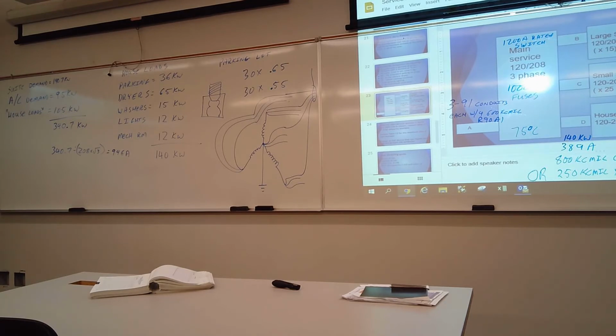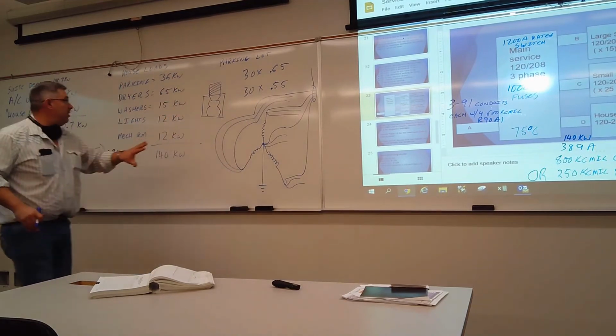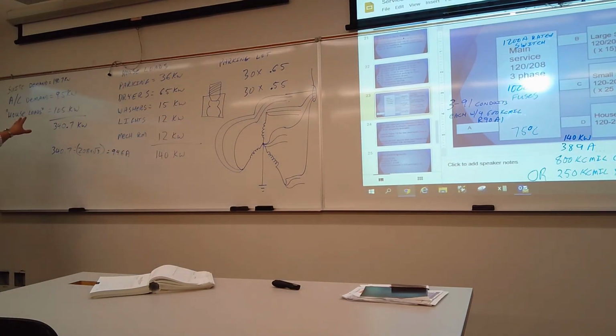Now, if it's separated out like this, we've got one feeder that's going to go out and feed all the large suites, and another one that's going to feed all the small suites. Let's say the large suites are the top 3 floors of the building, and the smaller ones are the next 4 floors. We put one central distribution for each. There's lots of ways it could be laid out. When you come out of your main service and you're doing feeders for a number of suites, you have to go back and go through that same process we used to calculate our main suite demand, right? Because this is your main feeder, these are suite feeders, right?